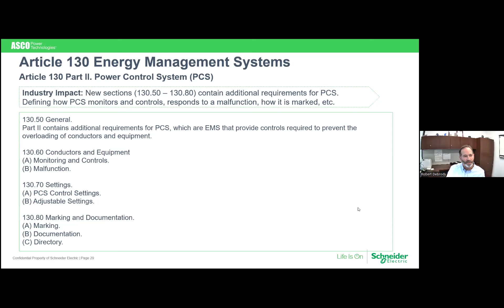Paragraph 702 is optional standby systems, automatic load connection. If you look off to the right here, there's a load management system designed to shed loads. It works with a PCS system or with an energy management system. So the changes here really just separate what an energy management system is and what a PCS does.